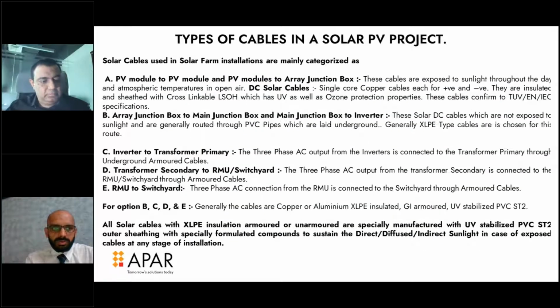Coming to solar cables, they are categorized into around 5 main modules. One is PV to PV and PV to array junction box—cables mostly exposed to sunlight throughout the day and night. These are DC solar cables, single core copper cables for positive and negative, insulated with cross-linkable zero halogen material, conforming to TUV, EN, and IEC specifications, offering UV and ozone protection. Then there's the array junction box to main, and main junction box to inverter DC cables, which are not generally exposed to sunlight—routed through PVC pipes and laid underground, generally using XLPE type cables.